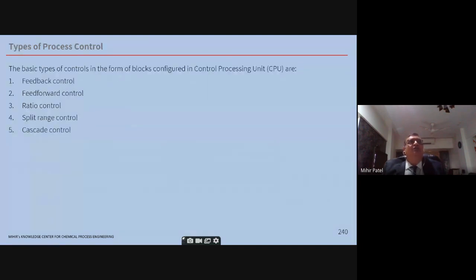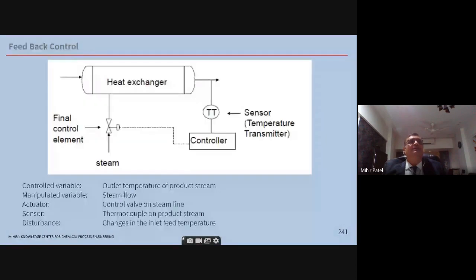Type of process control. So there are different types of process control, five types: feedback, feed forward, ratio control, split range, and cascade. So feedback control. As you can see, in the feedback control, the process stream has entered through the exchanger. At the outlet, you have the temperature sensor. Suppose it is set at 80 degrees, and if it becomes 82, feedback goes to the control valve, the steam valve is reduced, and 82 becomes 80 again. This has a negative because there is some lag in the control.